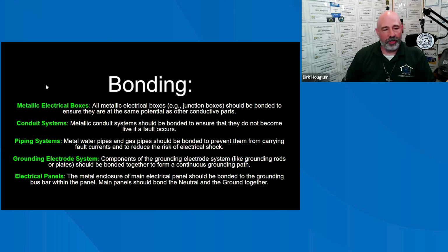That makes sense. Okay. Bonding metallic electrical boxes: all metallic electrical boxes and junction boxes should be bonded to ensure the same potential in conductive parts. Conduit systems should be bonded throughout. I like using conduit, especially metal flexible conduit, but you have to make sure that it's all bonded together so that everything has the same potential. A lot of times I'll use that metal conduit system as the ground. So when I ground things together, piping systems, metal water pipes and gas pipes should all be bonded together.